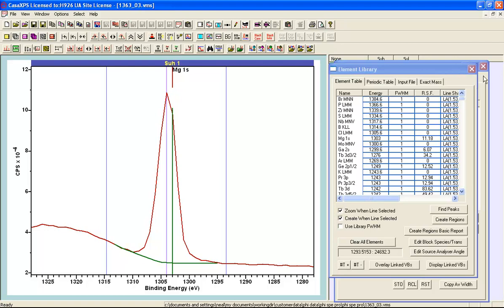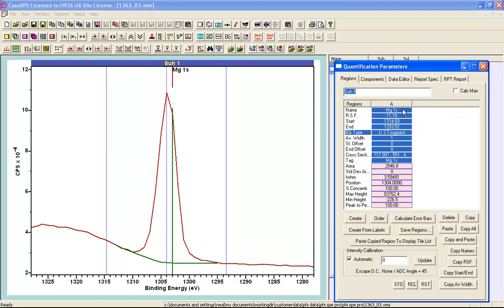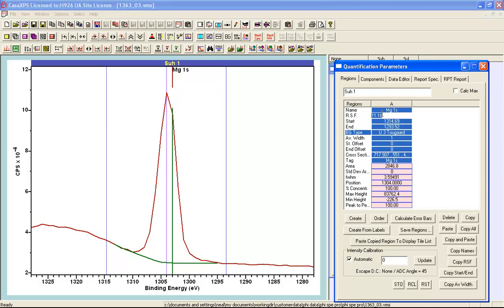The region that has been created, the relative sensitivity factor has been brought in which is a Schofield cross section. Since I have got a Schofield cross section here this means that I need to include an escape depth correction because the Schofield cross sections do not account for variation in intensity as a function of kinetic energy due to changes in the escape depth. Currently it is set to none. This would be the correct setting for the relative sensitivity factors in the Phi element library, but I am going to use the Schofield cross section.